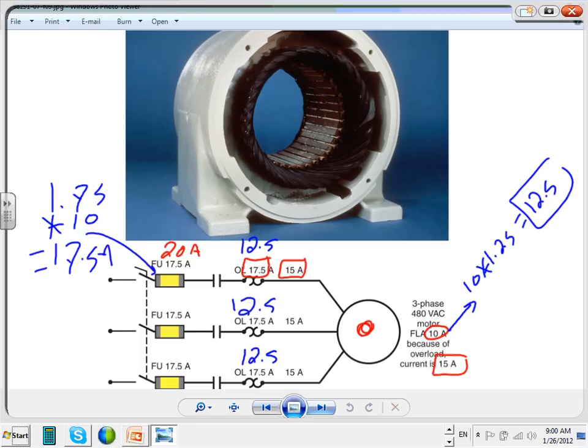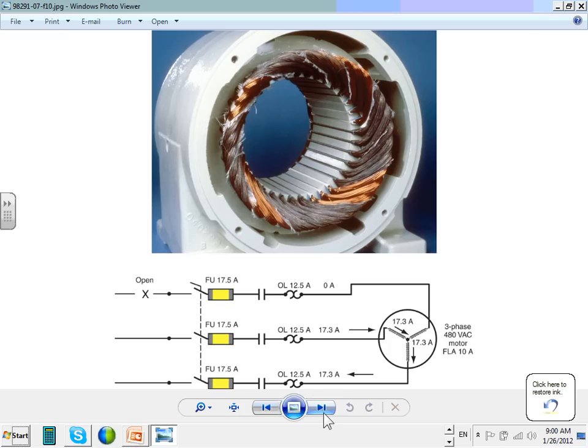Here's my fuse, 17.5 amp, but they don't make them, so that would allow you to go to the next standard. Any question, guys, about this? This will hopefully bring home the overload for you. I do this a lot with electricians because they set the overload, guys. Okay, so the other problem that you guys have to be aware of is single phasing.